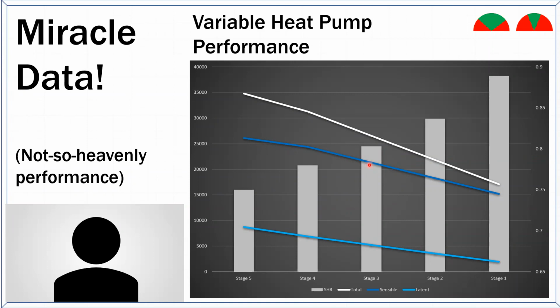Wow. See, I never thought about the law of unintended consequences like this. Well done, sir. And so there are units out there. I like to say if your mini split or inverter or multi-stage unit has a little water droplet on the control, you're probably all right, because that is a mode they can put it in that will not float the temperature of the evaporator to a warm temperature. It will slow the fan down relative to the outdoor unit and will do a better job of moisture removal as it ramps down.